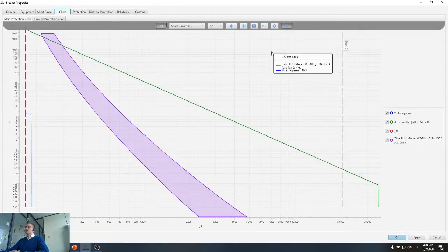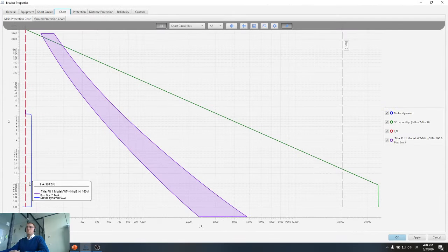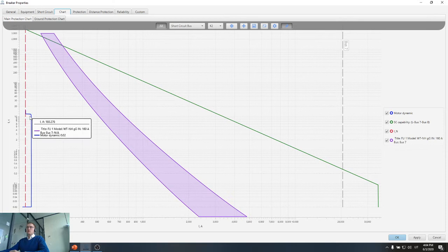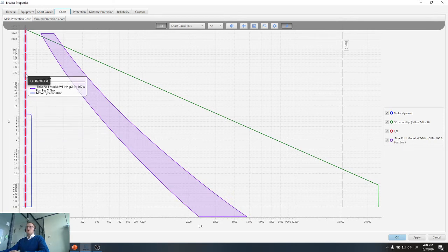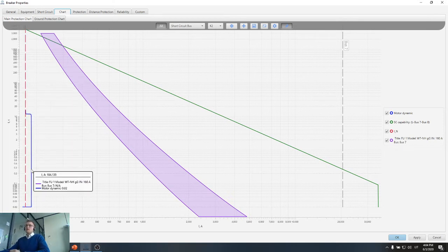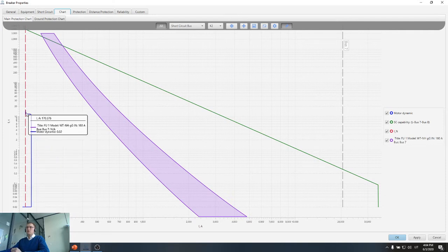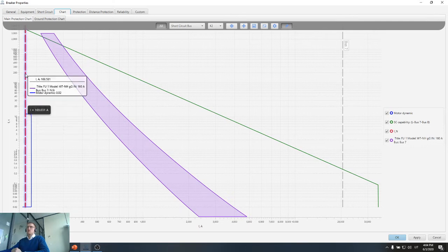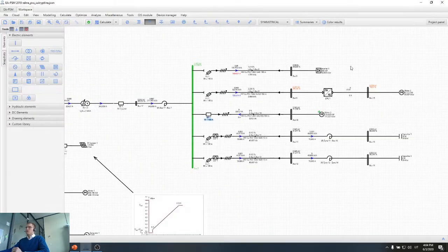So if I open the inverter current, we can see that during motor starting, the inverter current was a little bit bigger than during normal operation. This is because during motor starting, voltage was reduced, and in order to transmit the same amount of power, current has to increase. So the current is bigger here during motor starting, then it goes to the normal value. So the software definitely evaluates motor starting and also voltage dips during motor starting.